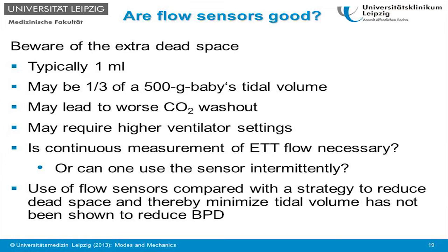The flow sensors introduce additional dead space. This is typically about 1 milliliters. This is probably 1/3 of a 500 gram baby's tidal volume. If you take away 1/3 of the tidal volume, you get worse CO2 washout, and this may lead to higher ventilator settings to compensate for the extra dead space. And if you have higher ventilator settings, this is probably less gentle to the patient's lung.